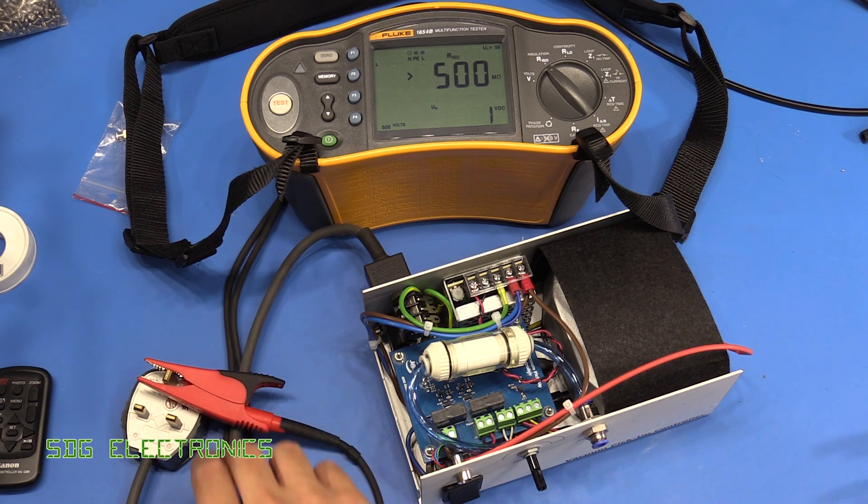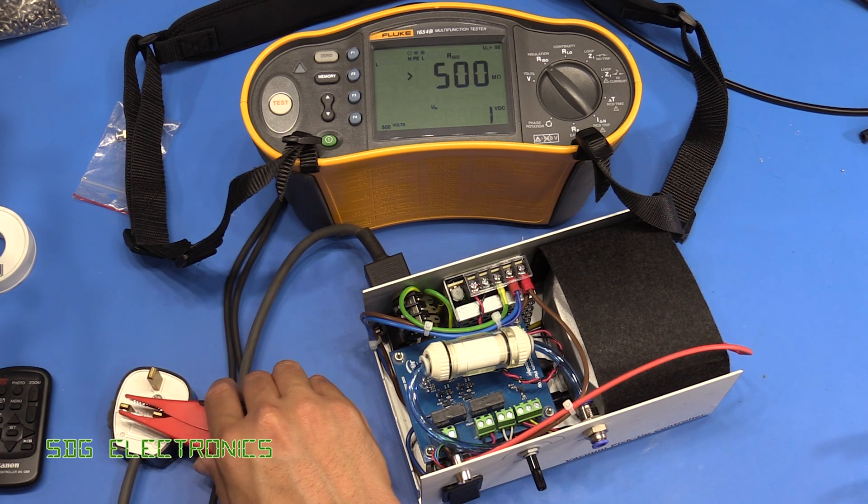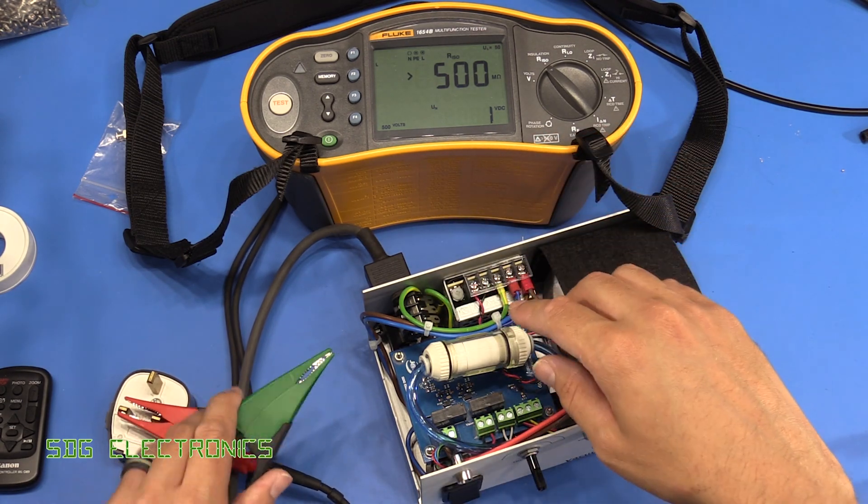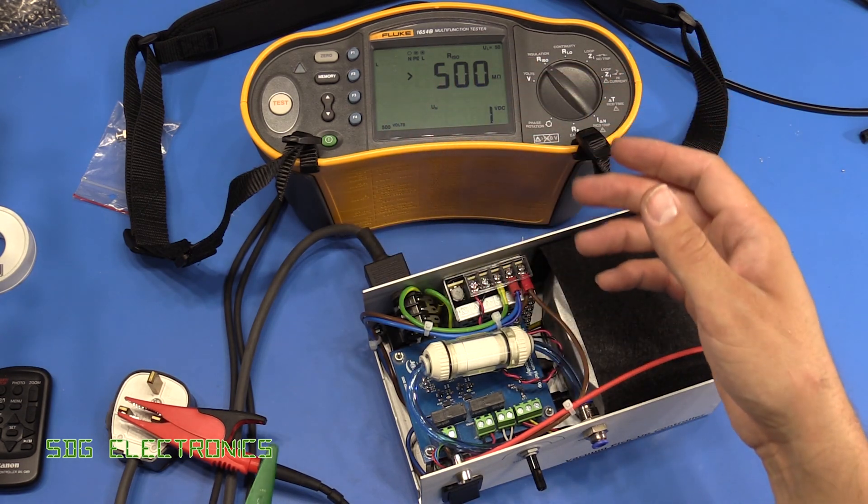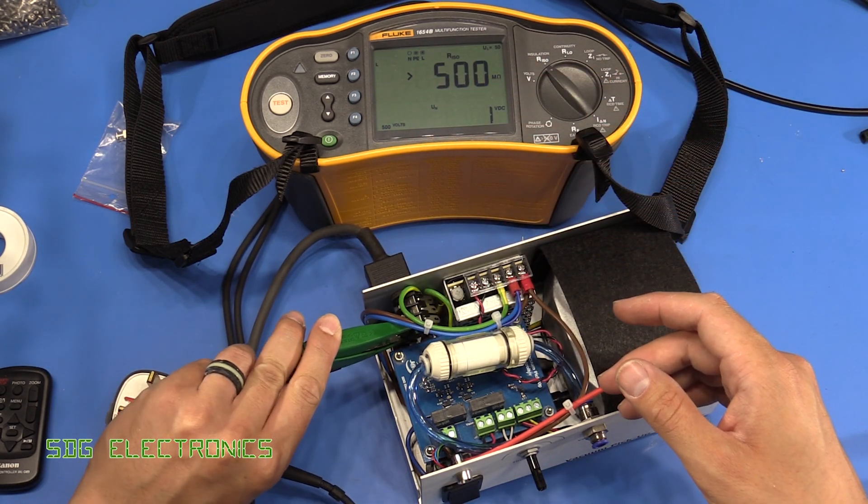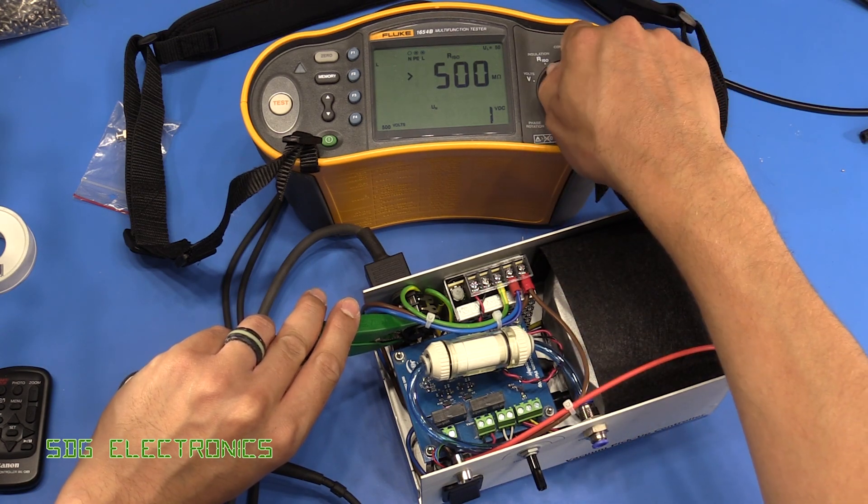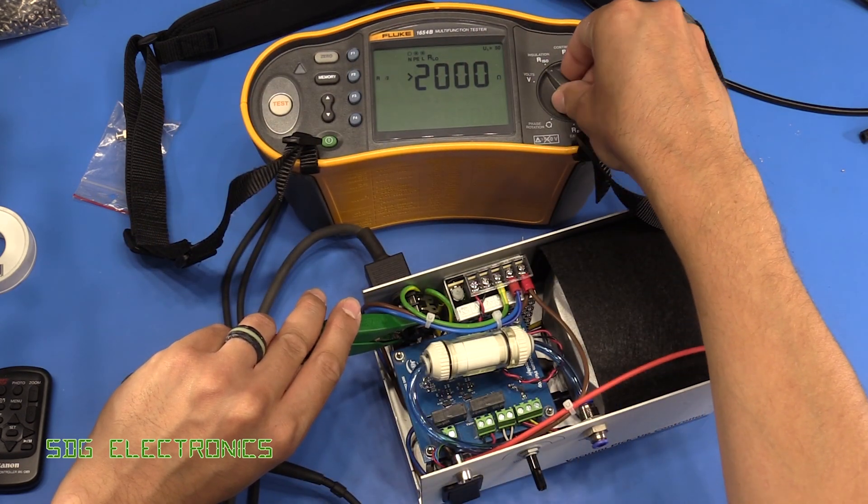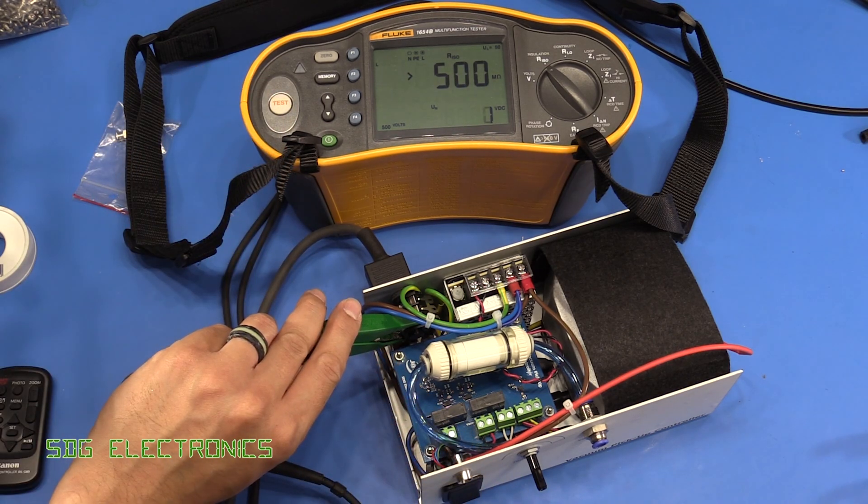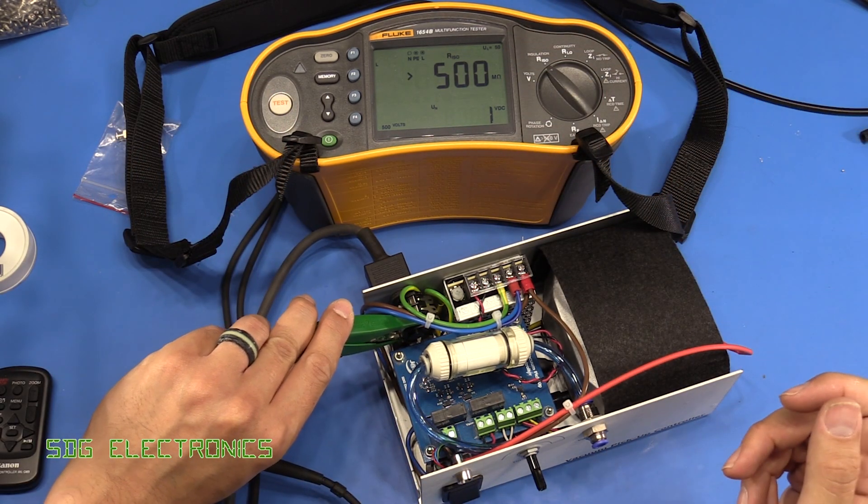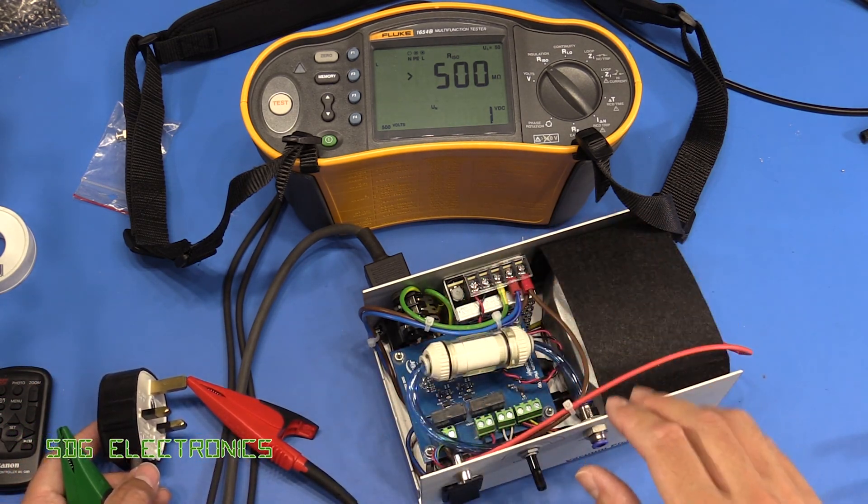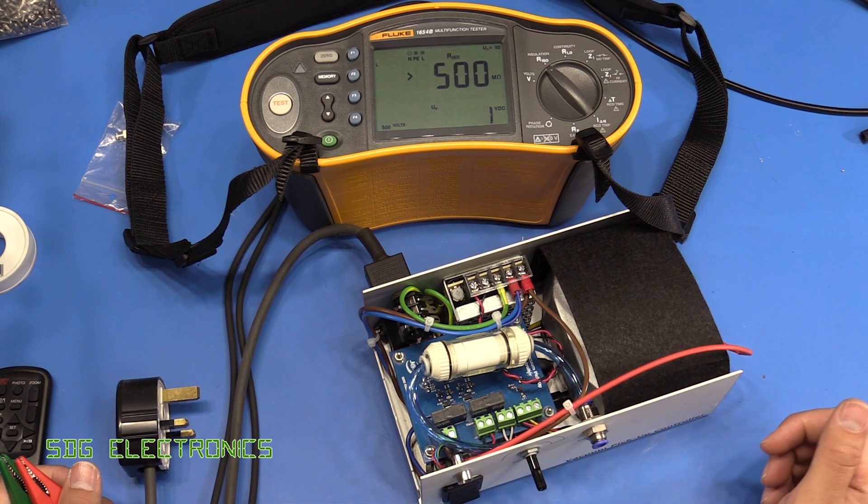One last test that we can do is do the same test, but test it between something on the extra low voltage side of the board just to make sure that when we plug in our foot pedal, we're not going to get a shock. So I'll try and clip this onto here. I'll set it to continuity first just in case it's a dead short. And no, nothing there. So we'll do an insulation test. And there we go. So greater than 500 mega ohms between the live and neutral pins and anything on the extra low voltage side. So we should be able to plug this in now.